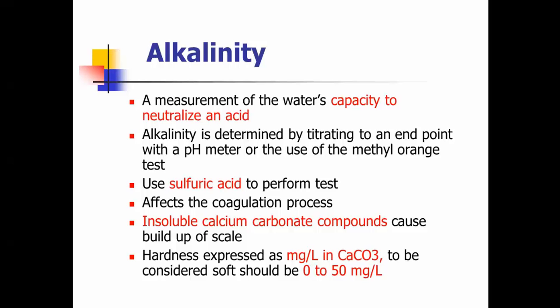Alkalinity is the measurement of the water's capacity to neutralize an acid, and on a line, that capacity to neutralize acid is known as alkalinity. Alkalinity is determined by titrating to an endpoint with a pH meter or the use of a methyl orange test. They also use sulfuric acid to perform the test. It affects the coagulation process. Also, you can get scale buildup with insoluble calcium carbonate compounds. And it's expressed as parts per million in CaCO3, and to be considered soft, it should be between 0 and 50 parts per million.